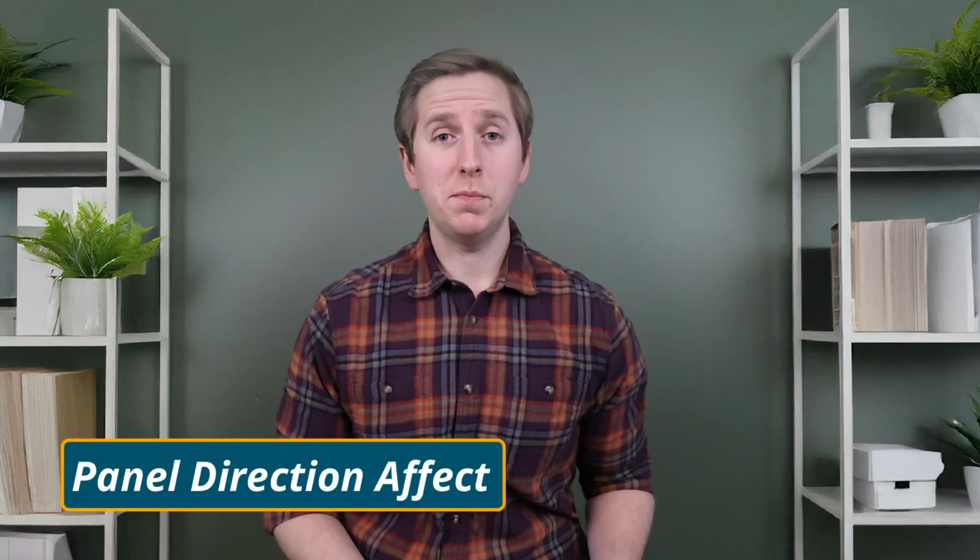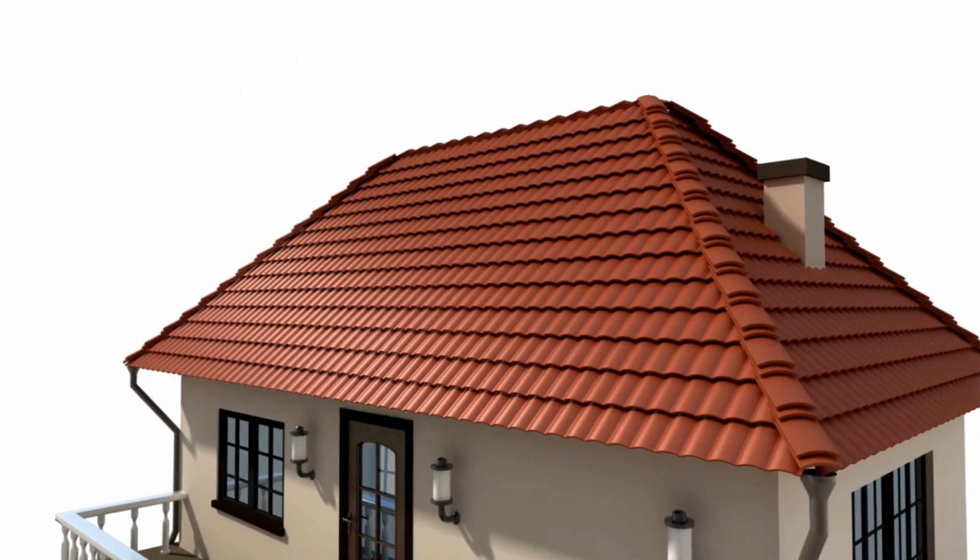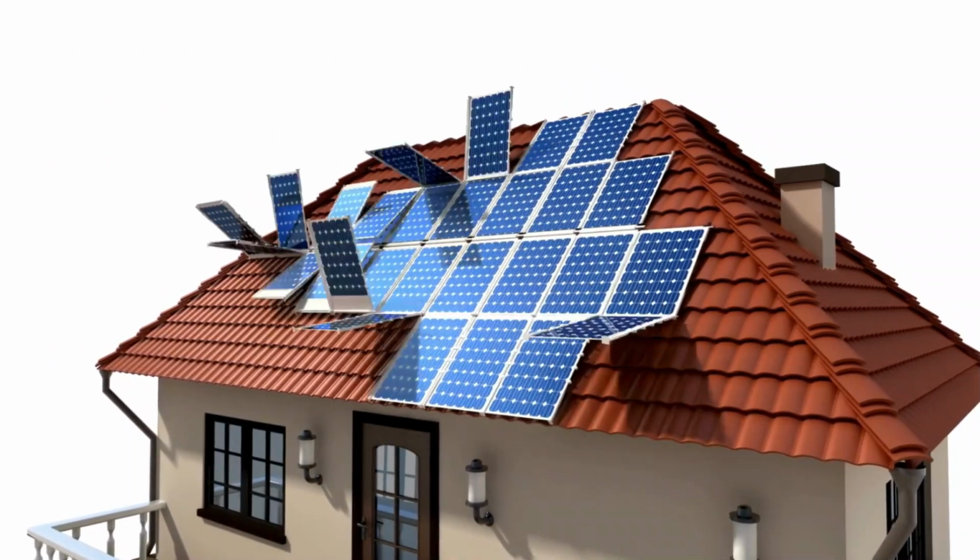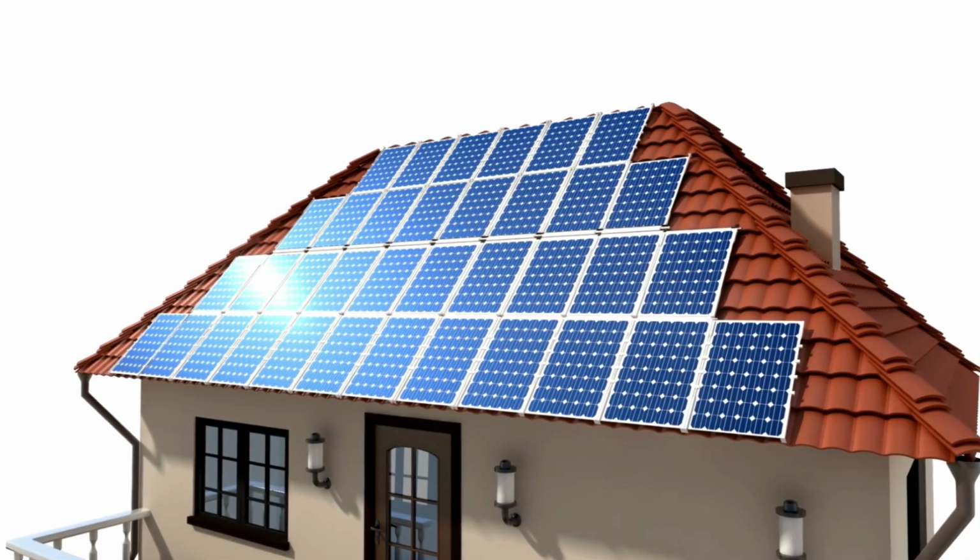Panel direction also plays a pretty important role in whether clipping will actually affect your system. We've previously published a video about the direction of solar panels that I'll link here for you to view as well. It's a great resource. When you have a system that all faces one direction, the sunlight hits it evenly and your production spikes immediately. So your system can reach that inverter maximum really quickly and then flatten out your curve, so you lose some energy. But if your system is a little more spread out, like you have some panels facing east, some facing west, your curve can be a little more smooth throughout the day because not a single one of those arrays is going to get you over the peak. They're not all in the maximum sunlight at any given point in time.